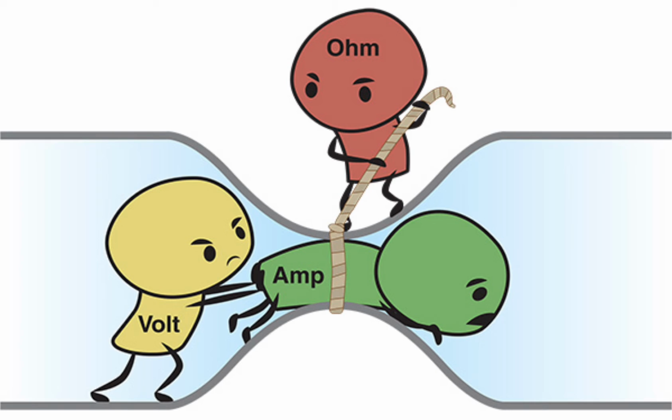A 24-volt lead-acid battery has how many cells? 12 cells, each cell 2 volts. What are the units that battery capacity is measured in? Amp hours. What should be the specific gravity of the electrolyte in a fully charged lead-acid battery? 1.275 to 1.300.